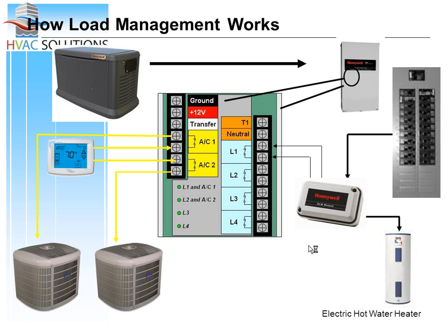So if I was to go through a sequence of events: the power goes off, the generator kicks on, we send power through the transfer switch, and we back up the customer's circuit breaker panel. Now, when I say we back up the panel, what we're really doing is giving the 115-volt circuits in a house power first. So if I was to ask you, what are 115-volt circuits in a house? Outlets come to mind, refrigerator, TV, sump pump, garage door, basic lights. So the first thing that happens is you get all the necessities, all the 115-volt circuits in the house.